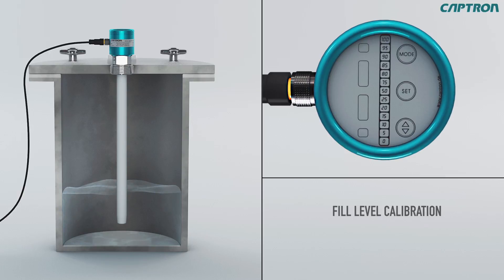The maximum alignment. Now 0% as well as 100% will light up red and MX. The now blinking value is the last maximum set value. Fill the tank now with between 25 and 95% of the desired measurement range. With up-down, you can now set the actual value of the fill level. As soon as you've confirmed the value with the set button, the green display will again stop blinking and the probe will jump after 5 seconds to the next step.